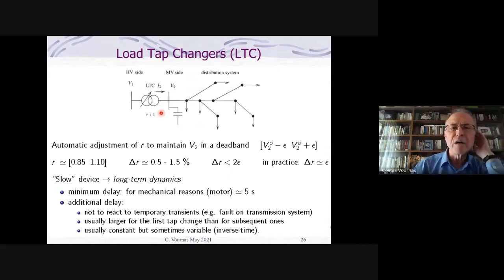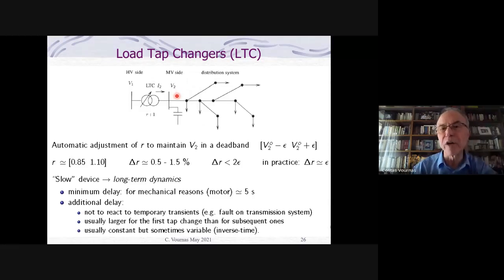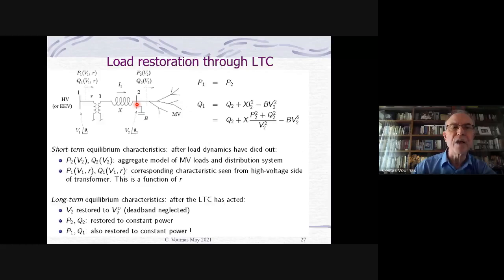This is what the tap changer will do. This is the distribution transformer, this is a distribution feeder. You see I can have compensation, I have different loads. But if I restore this secondary voltage to its set point, let's say V20, this means that I also restore the active and reactive power consumed here, so I restore the active and reactive power seen at the primary.